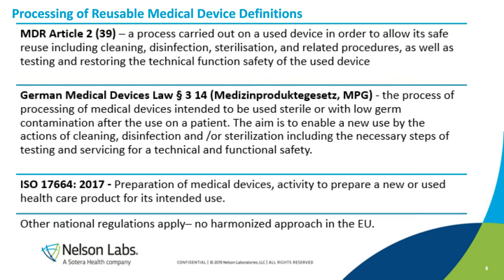According to ISO 17664, that was republished in 2017, preparation of medical devices is an activity to prepare a new or used healthcare product for its intended use. And those are the current definitions of reusable medical devices. And now other national regulations apply. And the problem with this information is that there's really no standard approach in the EU at this point.